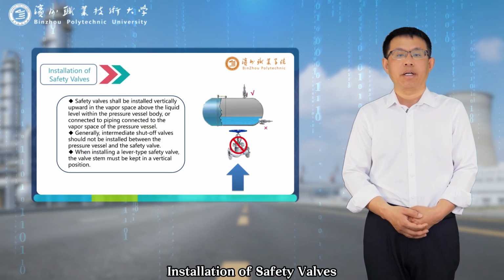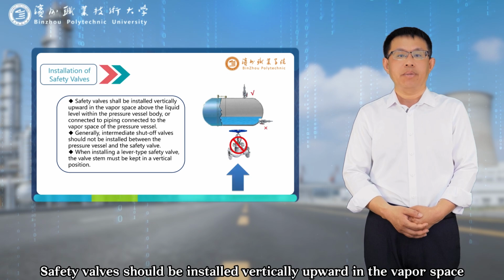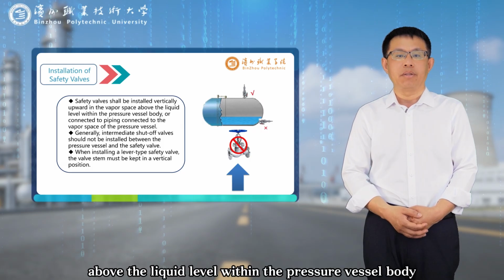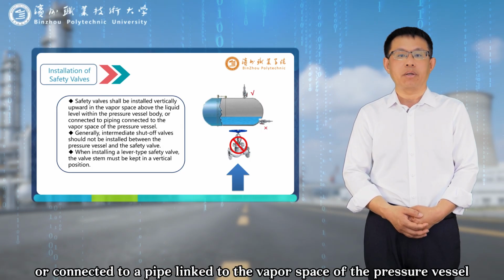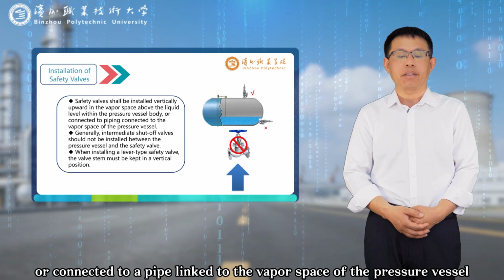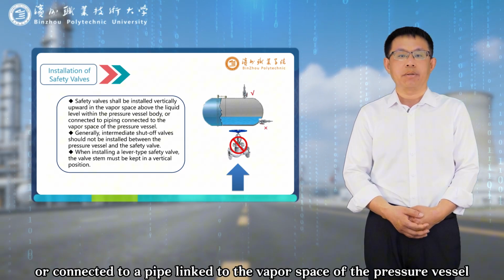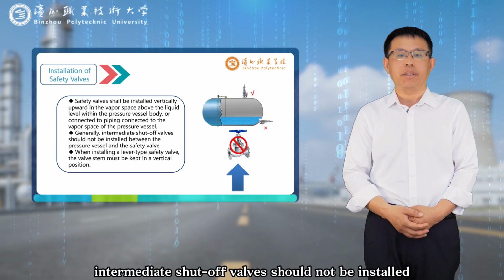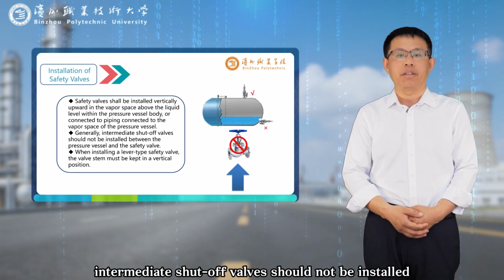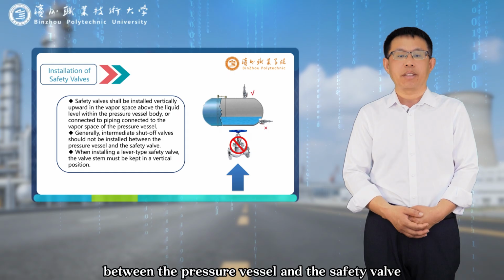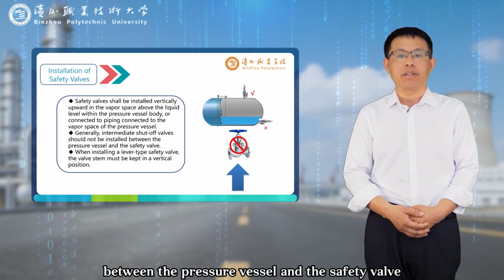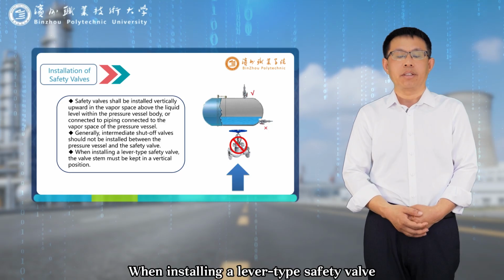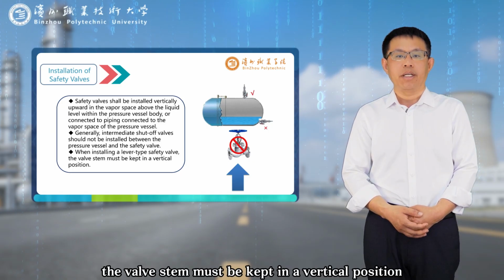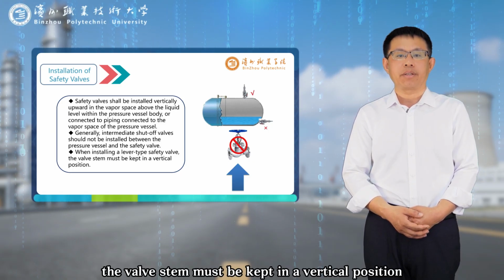Installation of safety valves. Safety valves should be installed vertically upward in the vapor space above the liquid level, within the pressure vessel body, or connected to a pipe linked to the vapor space of the pressure vessel. Generally, intermediate shut-off valves should not be installed between the pressure vessel and the safety valve. When installing a lever-type safety valve, the valve stem must be kept in a vertical position.